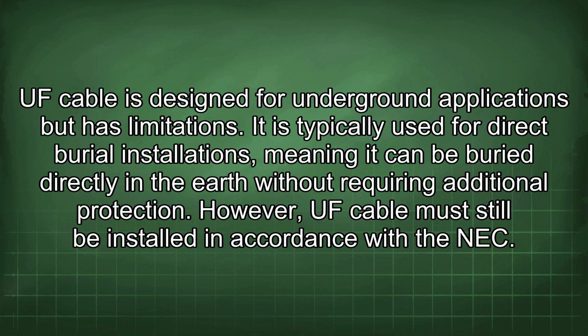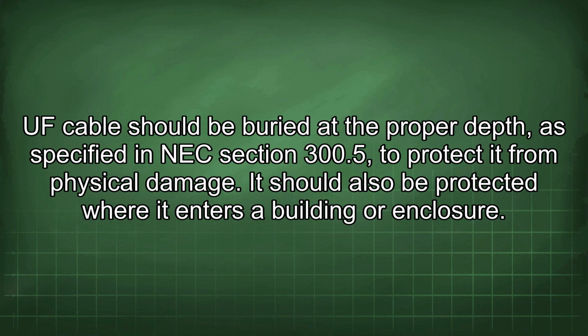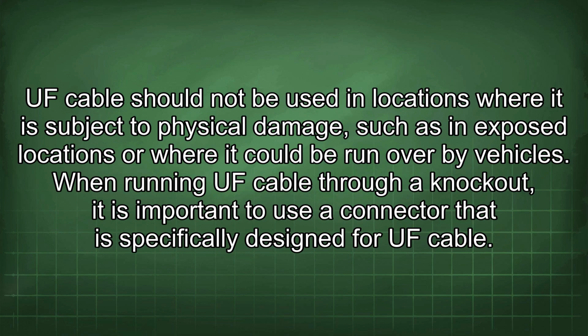However, UF cable must still be installed in accordance with the NEC. UF cable should be buried at the proper depth, as specified in NEC section 300.5, to protect it from physical damage. It should also be protected where it enters a building or enclosure. UF cable should not be used in locations where it is subject to physical damage, such as in exposed locations or where it could be run over by vehicles.